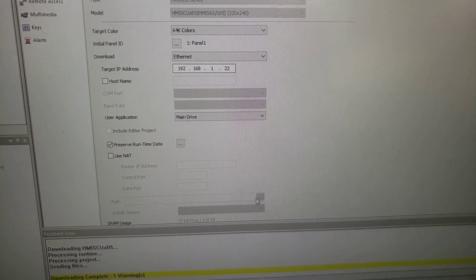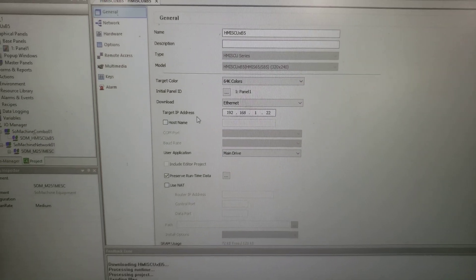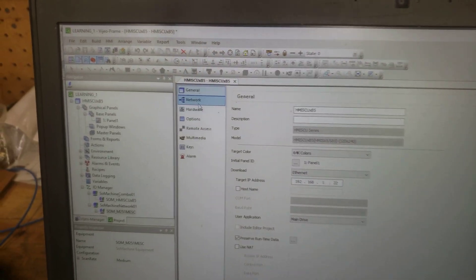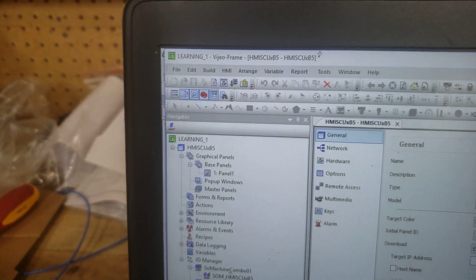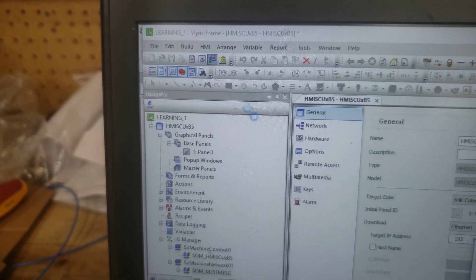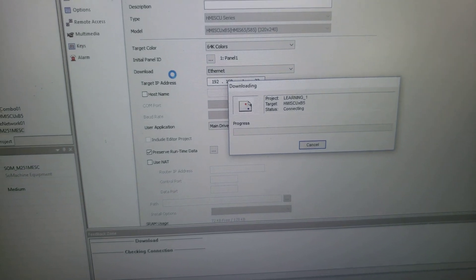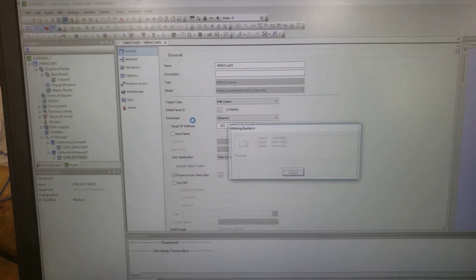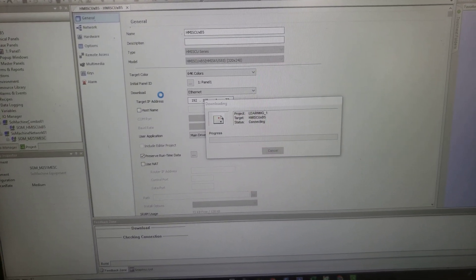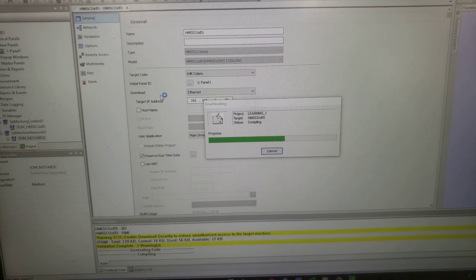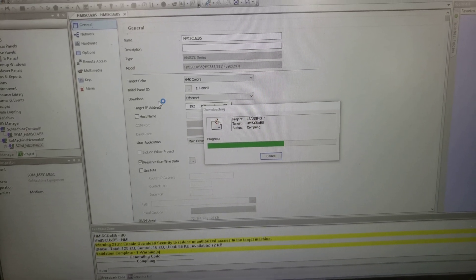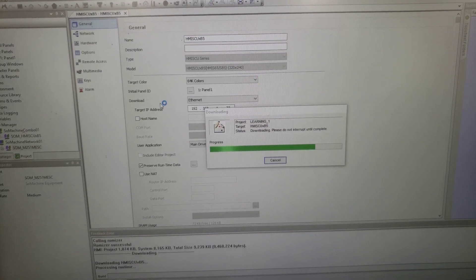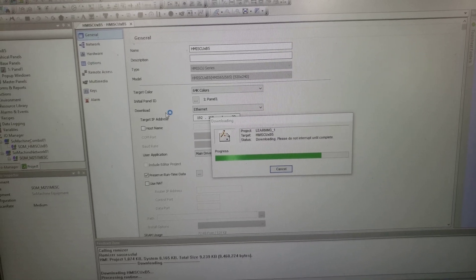Guys, I've been fighting this for days and I know it's stupid that I should have seen that box before, but you don't expect something like that on an HMI that's attached to the equipment. So we'll download all and it'll take it a second to do that. But you don't expect an HMI that's directly connected to the equipment to cause this problem on a local subnet.